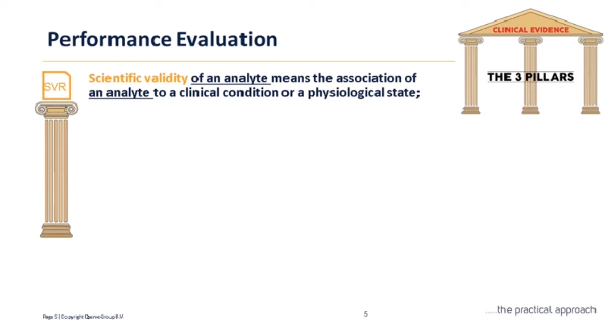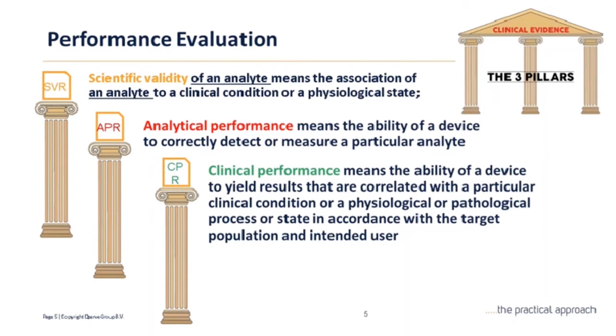So scientific validity associates the analyte you're trying to measure to your clinical condition or physiological state, whereas the analytical performance means the ability of your device to correctly detect or measure a particular analyte. So here we might be looking at analytical sensitivity and specificity, for example, whereas our clinical performance means the ability of the device to yield results that correlate with a particular clinical condition or a physiological or pathological state in accordance with the intended population and the intended user. So this could be our clinical diagnostic sensitivity, specificity, positive predictive value, that sort of thing.